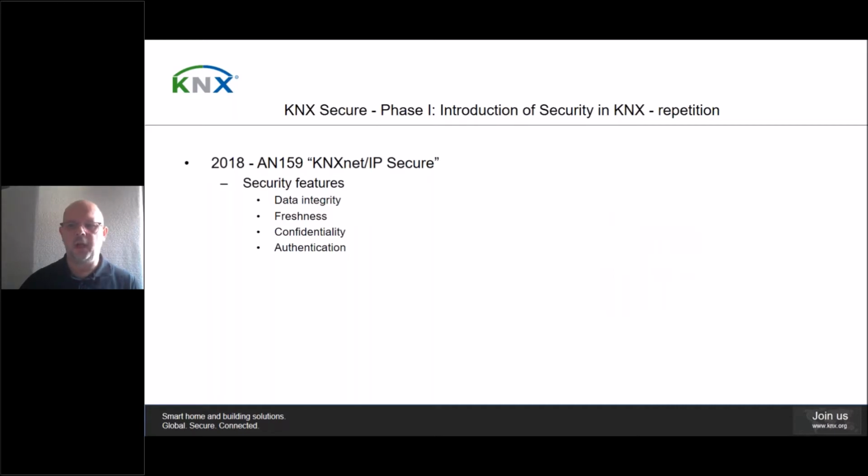Authentication. This allows that the communication partners are able to trust each other. KNX IP Secure offers server authentication, client authentication, and group authentication, which builds a group of trusted devices. In group authentication, every participant that proves knowledge of the secret backbone key is considered a legal member of the KNX IP routing multicast group. Communication modes. KNX IP Secure solutions are foreseen for Unicast, KNX IP device management, and KNX IP tunneling, as well as for multicast, that's KNX IP routing.